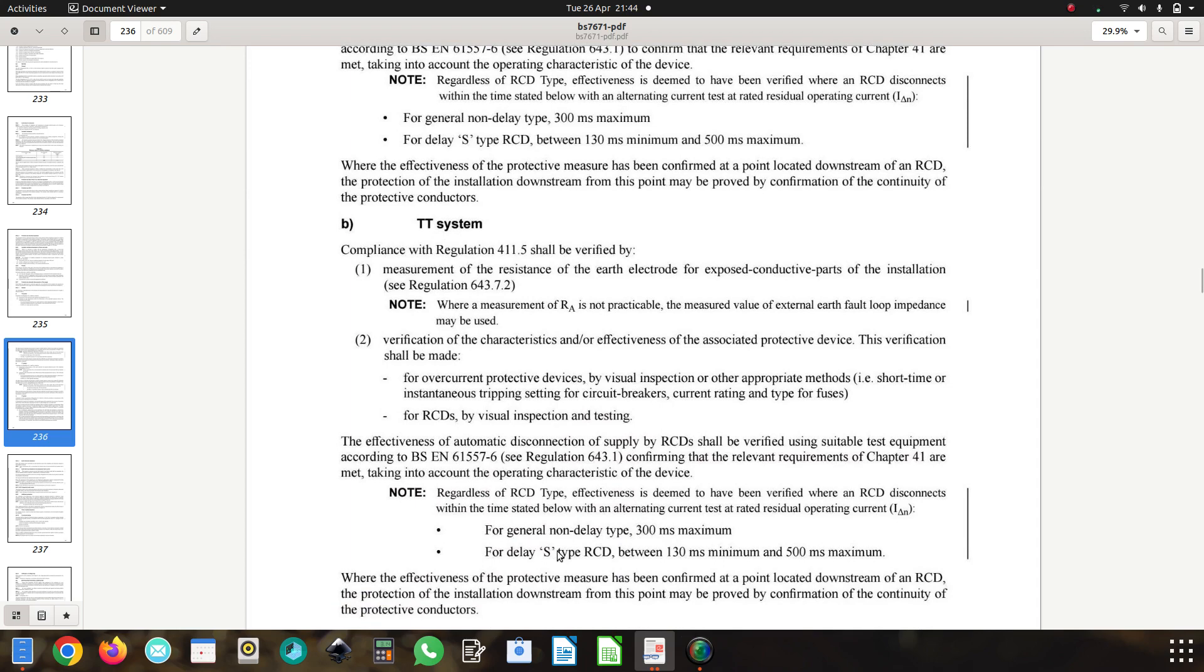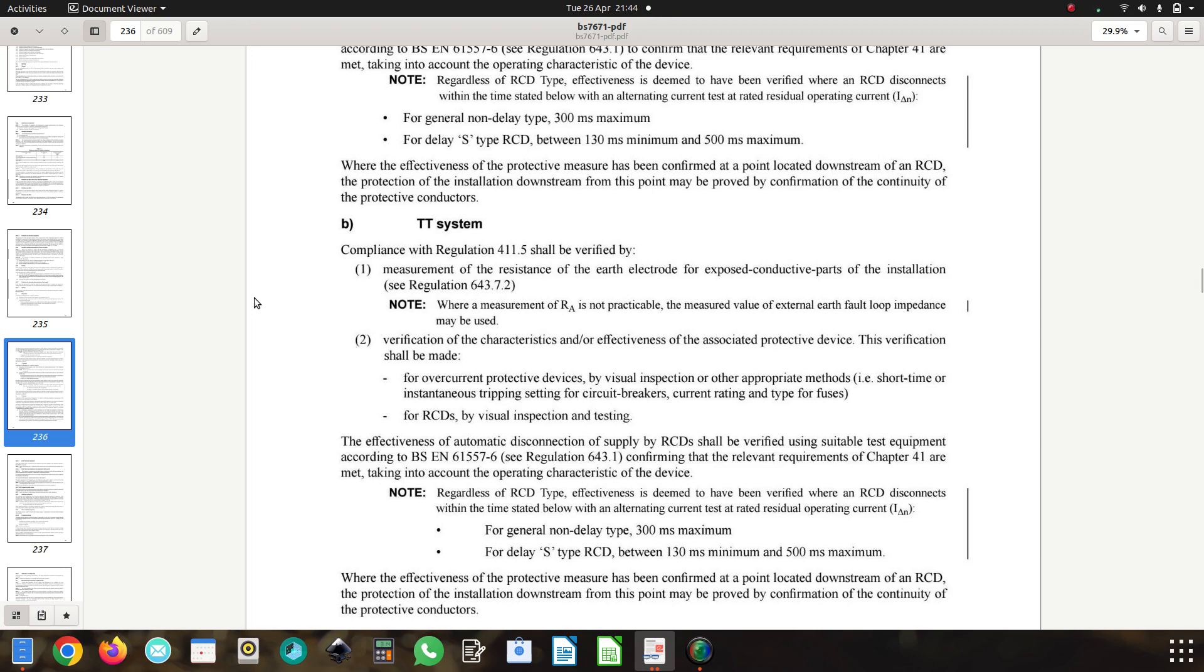Do we feel that that needs to be changed to 200 milliseconds to comply with the disconnection time for the particular circuit? I do. I think it needs to be 200 milliseconds there, because if I've got an RCD that's disconnecting at 250, yes it's lower than 300 milliseconds, but it still needs to be less than 200 for it to comply with table 41.1.